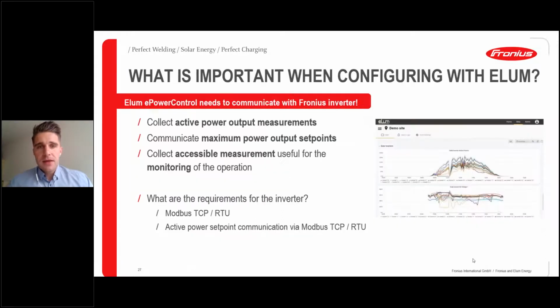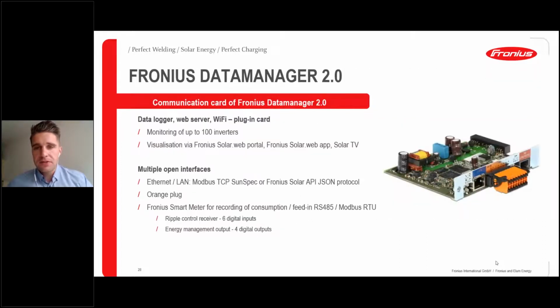What is important when configuring with Elum energy? We need the communication with Elum. It is very important to collect the active power output measurements and set the right output set points. We have to collect the accessible measurements useful for monitoring the operation. The key fact is the requirements of the inverter: we communicate via Modbus TCP or Modbus RTU, and all the settings can be done via these communication terminals. We from Fronius are perfectly prepared.